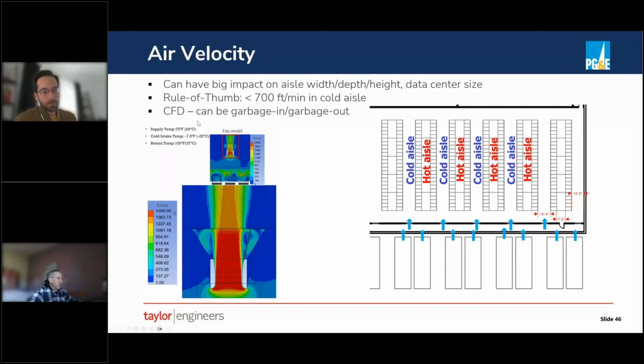And all I could say is that a CFD model can easily be garbage in, garbage out if you're not properly accounting for those micro zones of negative pressure and the fan curves of the servers. We use a rule of thumb of 700 feet per minute, sometimes even 600 feet per minute. You don't want your air going faster than that down the aisle because you have this risk of starving servers. Yeah, so highest velocity at the cold aisle entrance is where you need to be concerned.